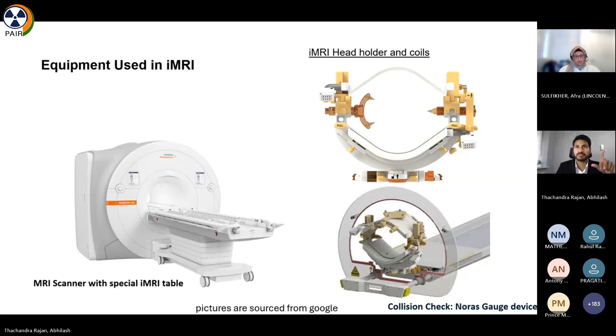And on the right side, we can see the IMRI head holder. We can see 3 spokes which will connect to the patient's head and secure it, and we can place the coils. They will be 8-channel coils, one above and one below. Intraoperatively, we use these coils to take the pictures of the brain, whereas in the pre-op scans, we use the standard MRI coils. In the bottom image, we can see there is a Noras Gauge device used around this coil. Once you connect the coils, we need to make sure that this setup will fit inside the bore of the magnet, which is around 70 centimeters. So we have this gauge equivalent to the size of the magnetic bore, and then we can make sure that once we transfer this patient back to the MRI room, the patient will fit inside the MRI portion.